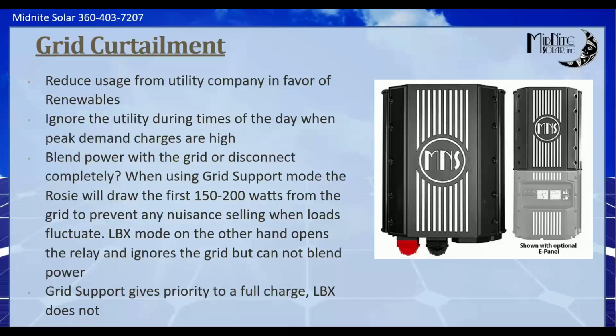Grid support, for example, will blend power with the grid. Some of the modes like LBX disconnect from the grid. So there's reasons for both of those, and we'll talk about them. One of the things to keep in mind when you are using grid support is that grid support is a form of sell. What grid support does is it sells out of the inverter until the loads are satisfied, and it tries to ride right on that hairy edge of not exporting but powering all your loads. What's been found over the years is every inverter that does this needs some amount of offset, where the first amount of power always comes from the utility grid, and then we power the loads. Because if you have, say, a 5,000 watt clothes dryer on and the electric element shuts off, that bounce for just a split second could cause the Rosie to sell to the grid if it doesn't have a little bit of room to work. I call it a forward bias, but it's the first 150 to 200 watts will come from the utility grid.